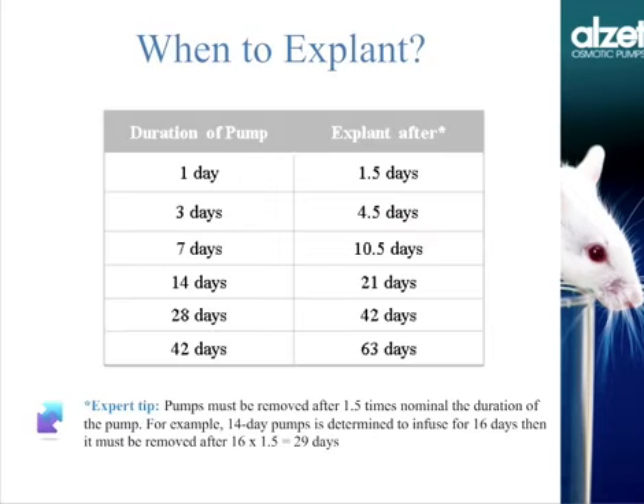And here's what I mean when I say 1.5 times. Let's say, for example, you have a 14-day pump like model 2002. Then you'll have to remove this pump after 14 times 1.5, or 21 days. With a 28-day pump, you'll have to remove it at 42 days. Now keep in mind that this explant date refers to the nominal duration of the pump and not the actual duration.